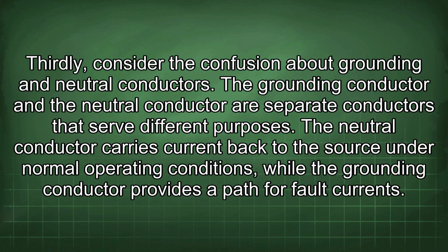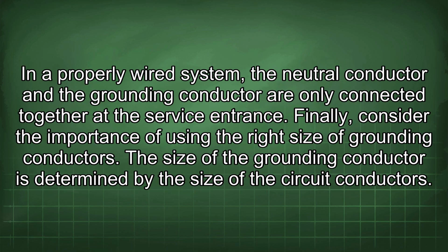Thirdly, consider the confusion about grounding and neutral conductors. The grounding conductor and the neutral conductor are separate conductors that serve different purposes. The neutral conductor carries current back to the source under normal operating conditions, while the grounding conductor provides a path for fault currents. In a properly wired system, the neutral conductor and the grounding conductor are only connected together at the service entrance. Finally, consider the importance of using the right size of grounding conductors.